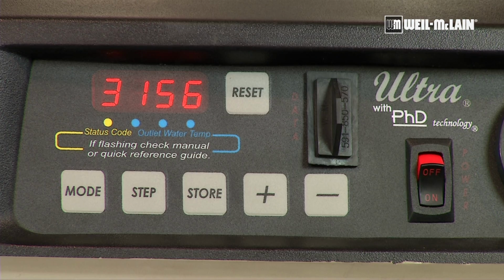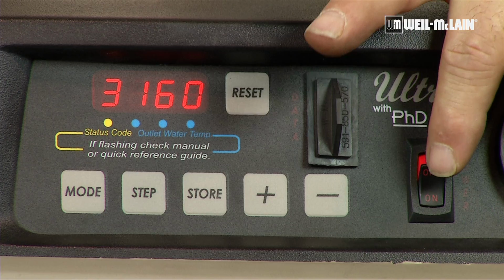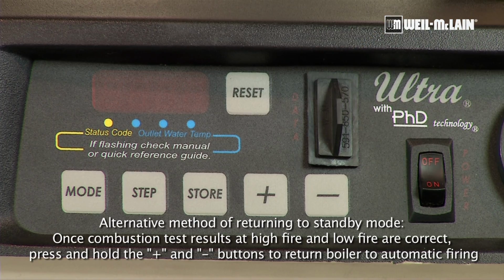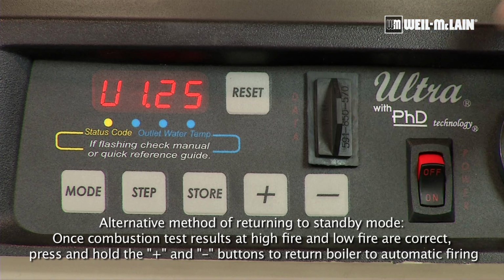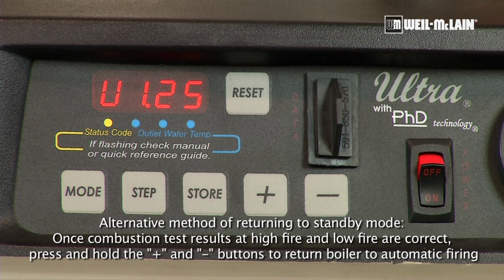To lock the controller back up and get out of the technician's level, there's two ways available for us. Number one, if we don't touch a button for 10 minutes, it'll automatically lock up. Number two, if we power cycle the boiler, it will lock itself up. Power cycling the boiler means nothing more than turning off the power switch to the boiler, leaving it off for about 15 seconds, and then reestablishing or turning power back on. At that point, it will go through its loading menu, but we have locked the control back up.